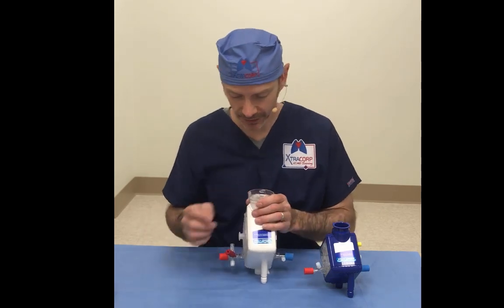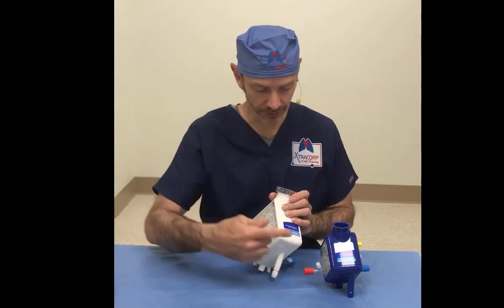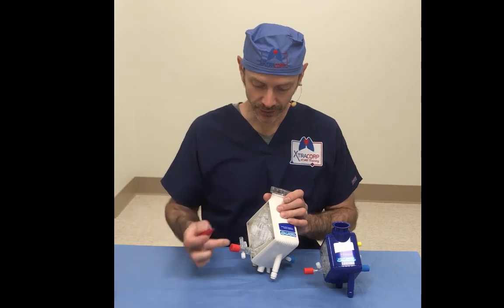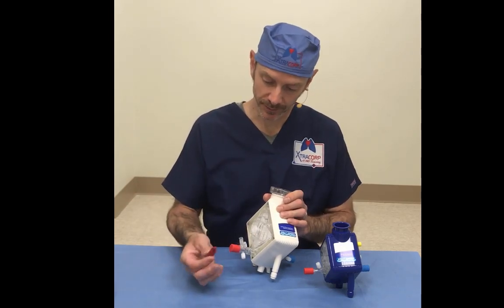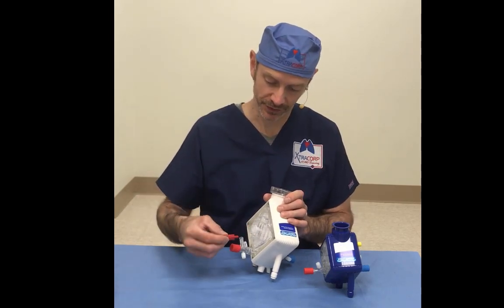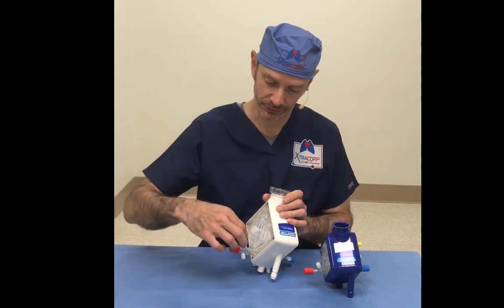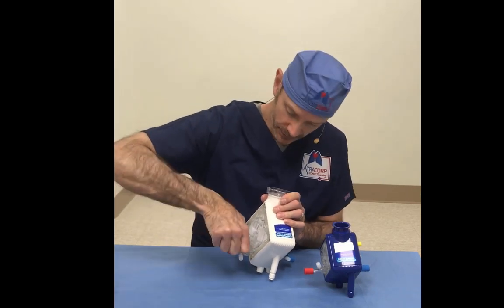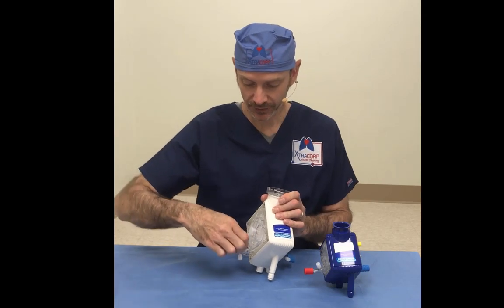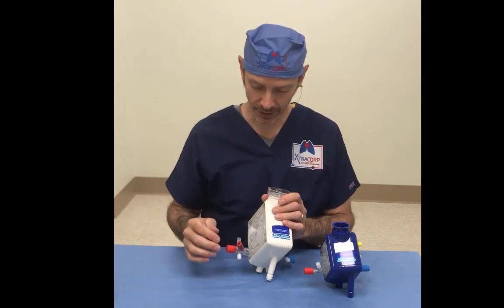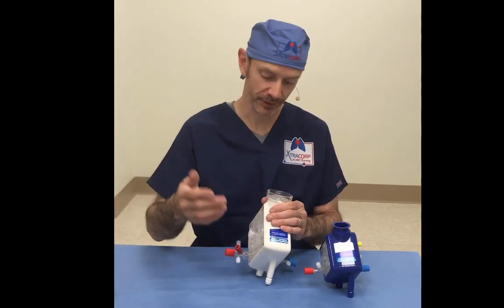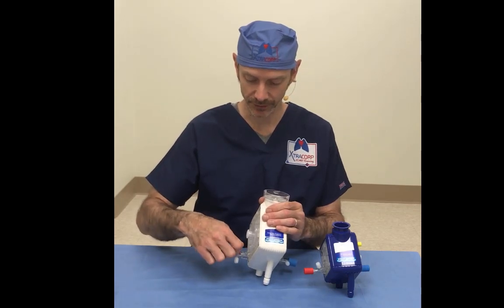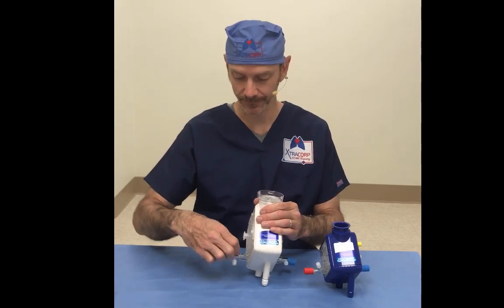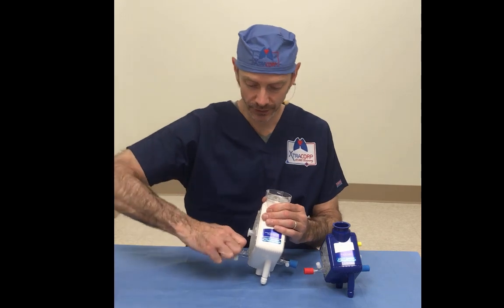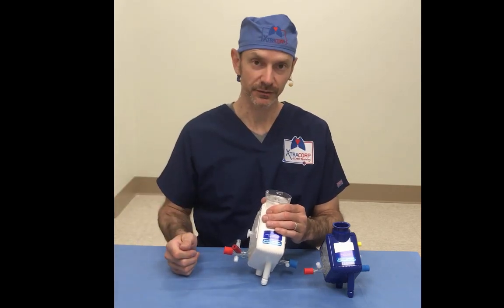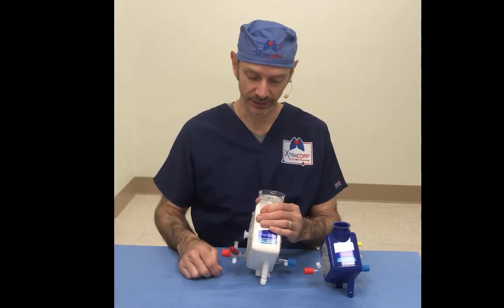The adult oxygenator has another couple ports over here that the pediatric does not. It has a 1/4 inch port with a luer cap. Well, it's a 1/4 inch slip fit, but this actually screws on like a luer and can be screwed tight. This would be used if you wanted to use this oxygenator in the operating room. You could use that for cardioplegia or some other supply, maybe a recirculation line if you wanted. But in the ECMO arena, there's generally no application for that, and it just remains tightly fit.